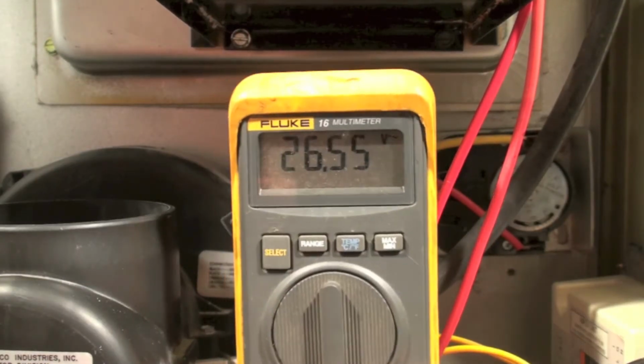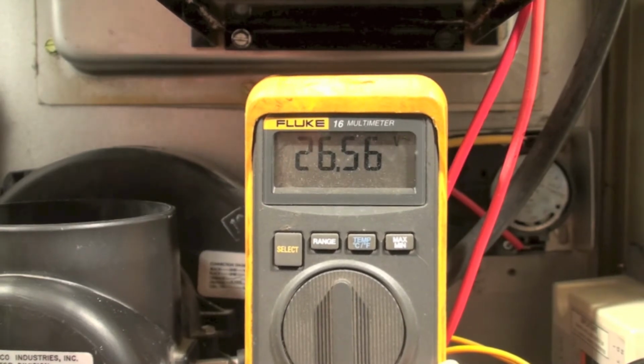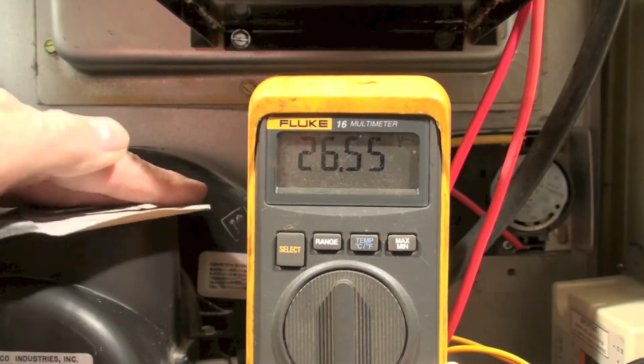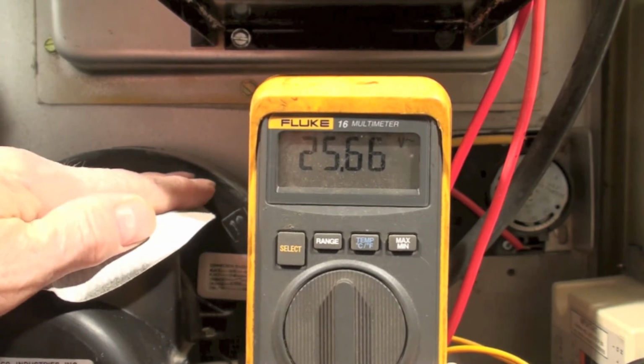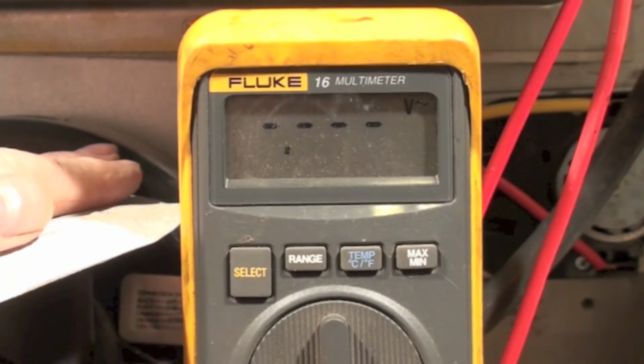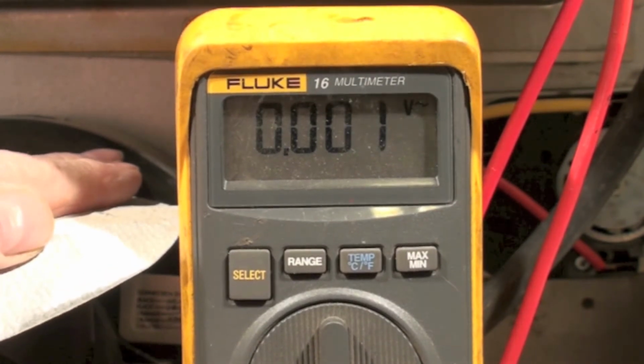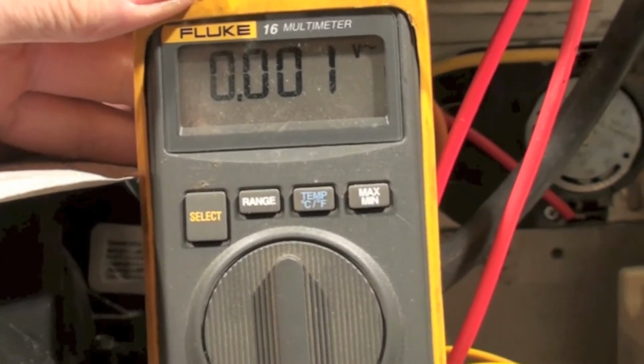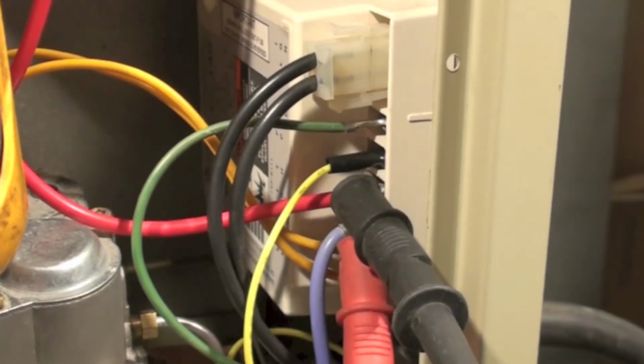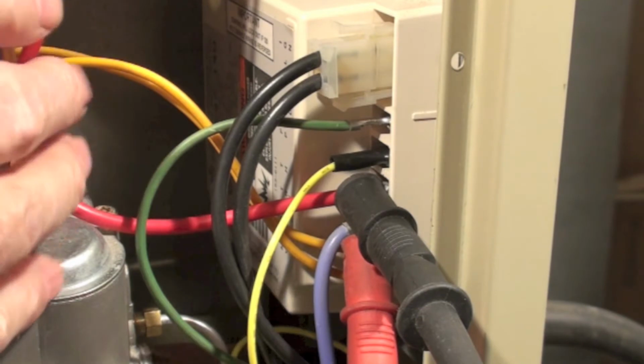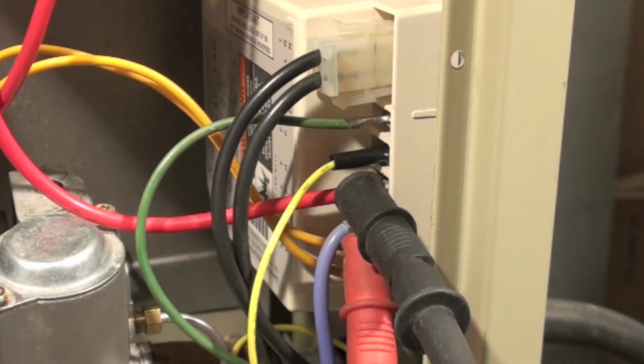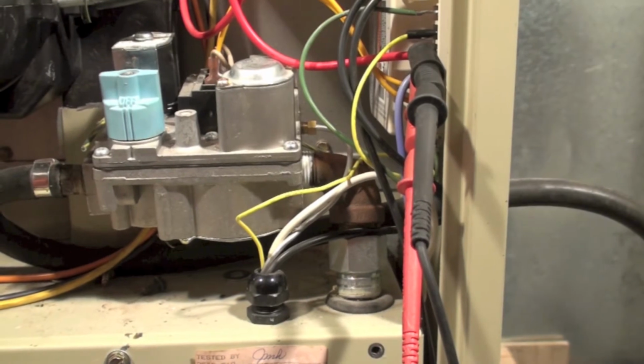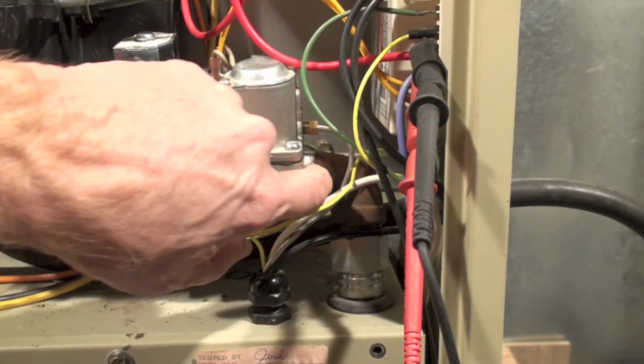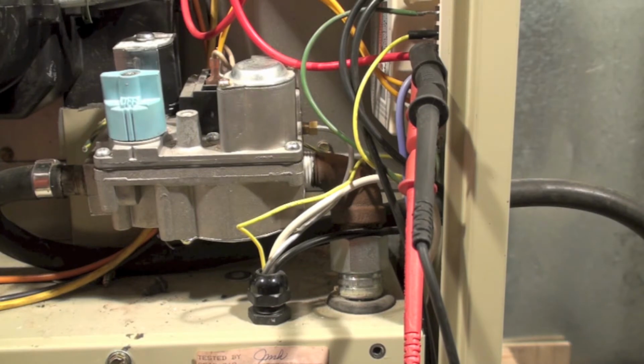Okay, how we're going to test this pressure switch is I'm going to cover this up and hold the cover over it. Okay, you can see it did shut off. I've got my probes right down there in TH and TR, so it tells me that works. Okay, when you have this thing fired up, you're going to want to check the manifold pressure by taking that plug out and putting your manometer on it. And it should be factory specs.